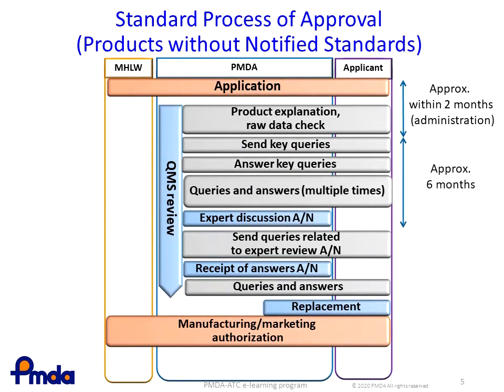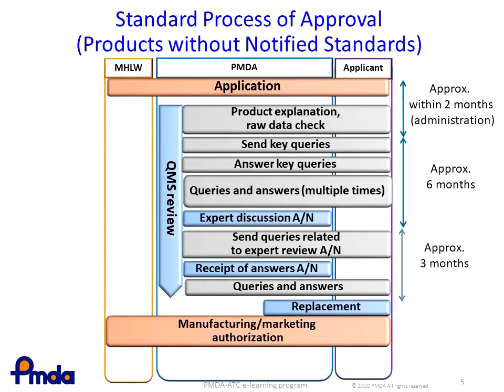Meanwhile, in the review category of non-standard products and companion diagnostics, expert discussion is held as needed during the review, and the approval process may take some extra time, as shown in this slide. In this case, after the discussions on key queries and answers between the PMDA and the applicant, expert discussion will take place, as needed, approximately within six months from the initial key queries from the PMDA. Then, further queries raised in the expert review will be sent to the applicant, and Q&A will continue for about three months.